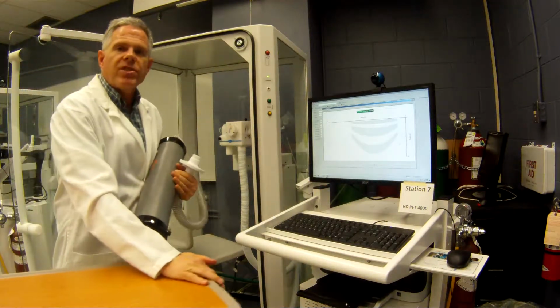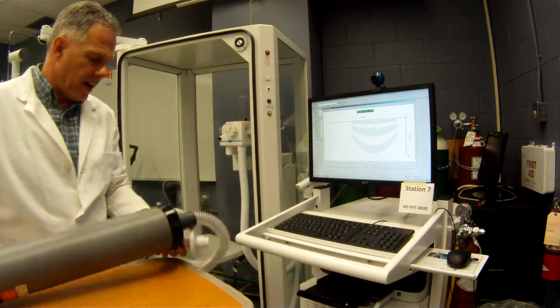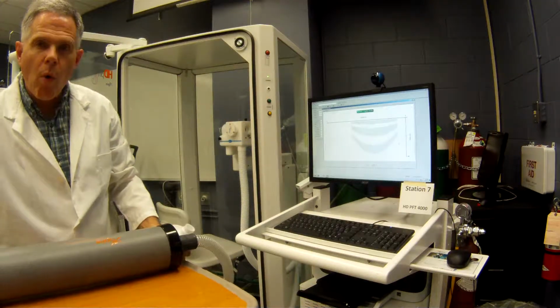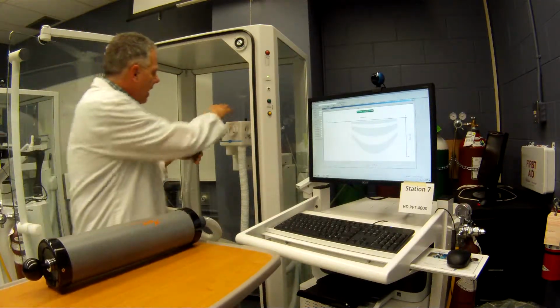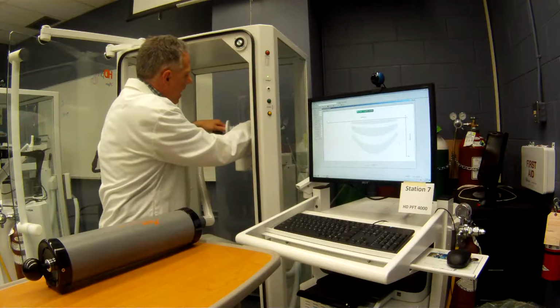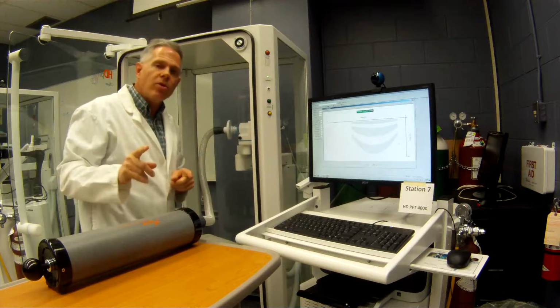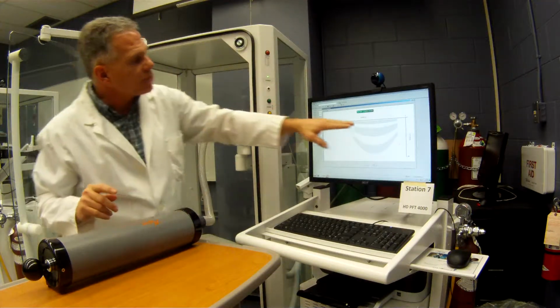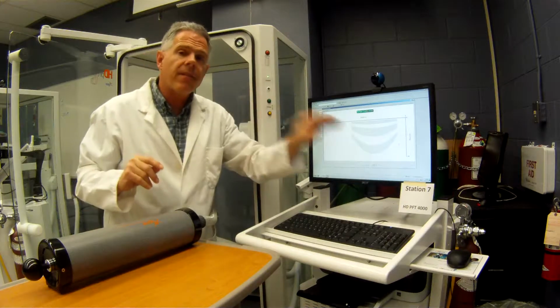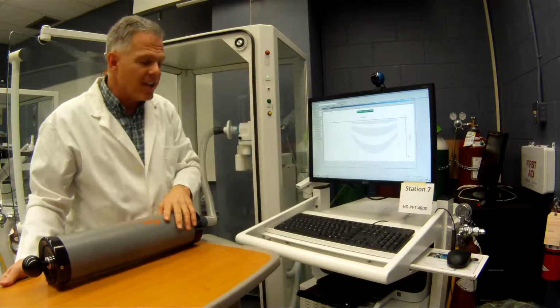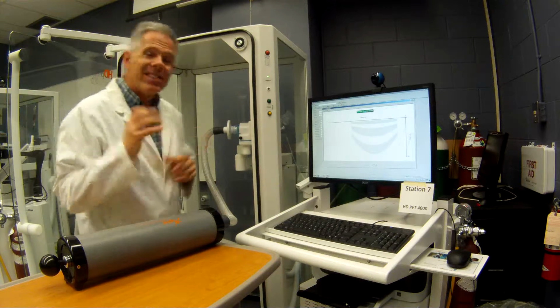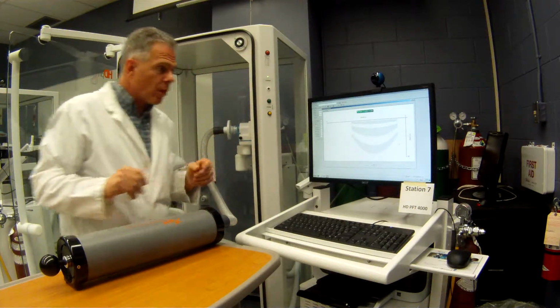And I find it best to use something like this. We've got a nice solid table to hold the syringe on, and we just hook that right up to our pneumotach like this. All right, so what we're doing with our calibration procedure is we're going to calibrate it for 3 different flow rates using a known volume. That's how it's going to establish that the pneumotach is working properly.